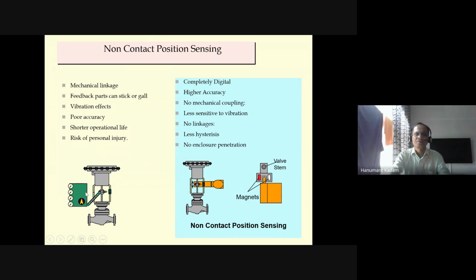This I have shown you, but the latest valves are coming with non-contact position sensing. Means there is no contact. This is not there. So mechanical linkage feedback parts can stick or gall, vibration effects, poor accuracy, shorten operational life, and there is a risk of personal injury. So these are the existing valve positioners with a contact type of stem linkage with a positioner. When we go for non-contact, you can see here non-contact position sensing. Completely digital, higher accuracy, no mechanical coupling, less sensitive to vibration, no linkages, less hysteresis, no enclosure penetrations.